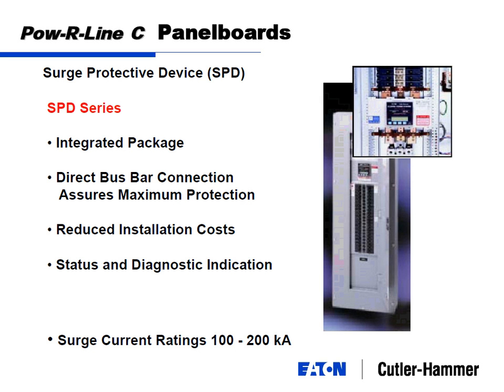And without looking at the actual numbers, you guys know if you've got a 480 volt system and your SPD is letting through the normal let through voltage of, say, 800 volts, and all of a sudden you increase it to 1200 volts because you got some cable in there, you can see how your protection can kind of wane. So it's always best to optimize that. And they come with a wide variety of interface, whether you want a light, a bell, a whistle, however you want to interface with that device.